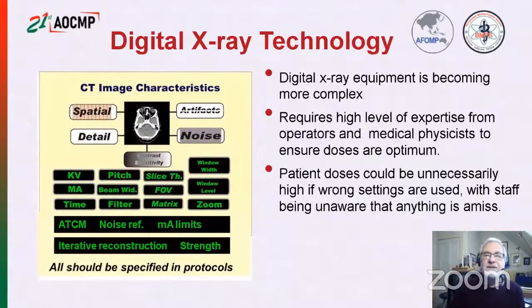Now, another problem with digital X-ray technology is that we have more and more dose-saving devices, but the digital X-ray equipment implementing these is becoming ever more complex. This requires a high level of expertise from both the operators and medical physicists to ensure that doses are optimum. Patient doses could be unnecessarily high if the wrong settings are used, and because the image appears essentially the same, staff will be unaware that anything is amiss.